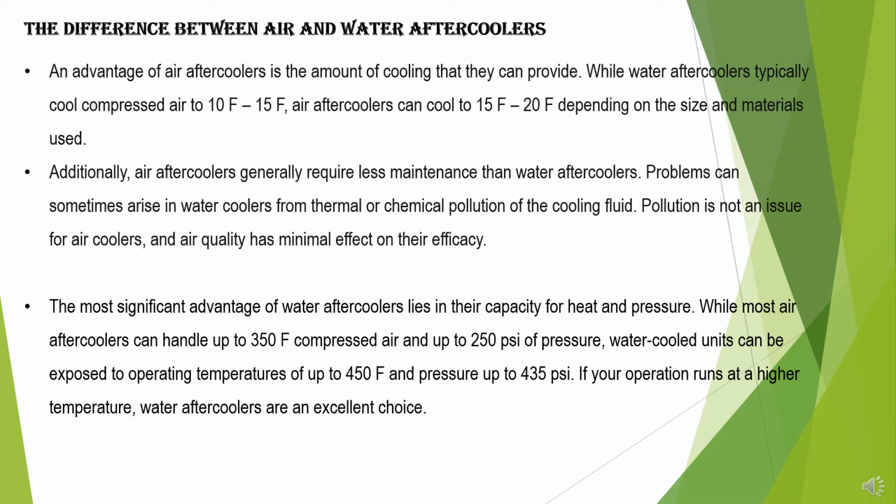The difference between air and water aftercoolers. An advantage of air aftercoolers is the amount of cooling that they can provide. While water aftercoolers typically cool compressed air to 10 to 15 Fahrenheit, air aftercoolers can cool to 15 to 20 Fahrenheit depending on the size and materials used. Additionally, air aftercoolers generally require less maintenance than water aftercoolers.